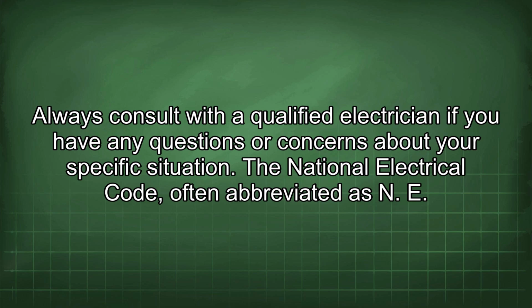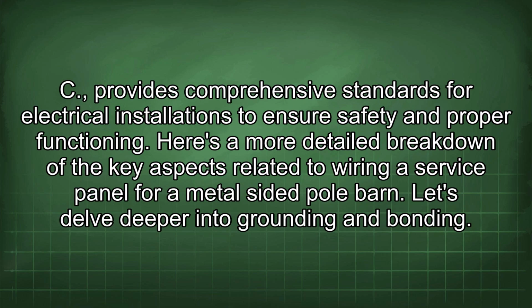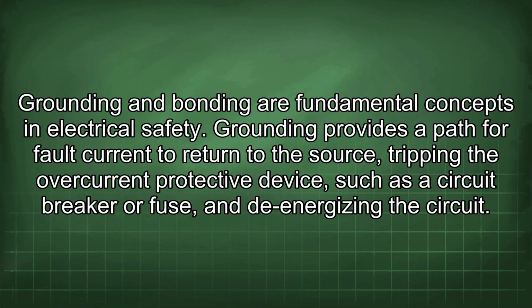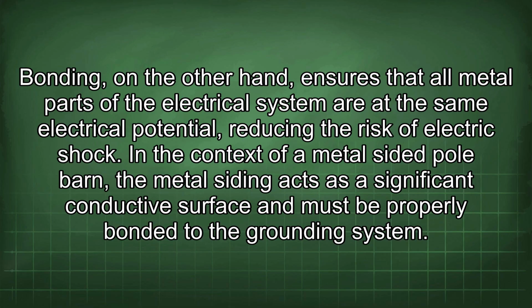The National Electrical Code, often abbreviated as NEC, provides comprehensive standards for electrical installations to ensure safety and proper functioning. Here is a more detailed breakdown of the key aspects related to wiring a service panel for a metal-sided pole barn. Let's delve deeper into grounding and bonding. Grounding and bonding are fundamental concepts in electrical safety. Grounding provides a path for fault current to return to the source, tripping the overcurrent protective device, such as the circuit breaker or fuse, and de-energizing the circuit. Bonding, on the other hand, ensures that all metal parts of the electrical system are at the same electrical potential, reducing the risk of electric shock.